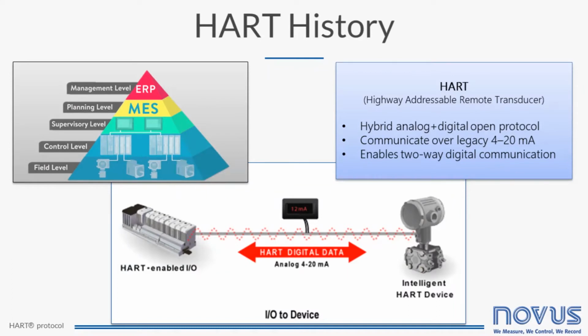Its most notable advantage is that it can communicate over legacy 4 to 20 milliamp analog instrumentation current loops, sharing the pair of wires used by the analog-only host systems, enabling two-way digital communication with smart microprocessor-based field devices. Due to the huge installation base of 4 to 20 milliamp systems around the world, the HART protocol became one of the most popular industrial protocols today. HART protocol has made a good transition for users who wished to use the legacy 4 to 20 milliamp signals but wanted to implement a smart protocol. The HART communication protocol is today a global standard for smart process instrumentation.